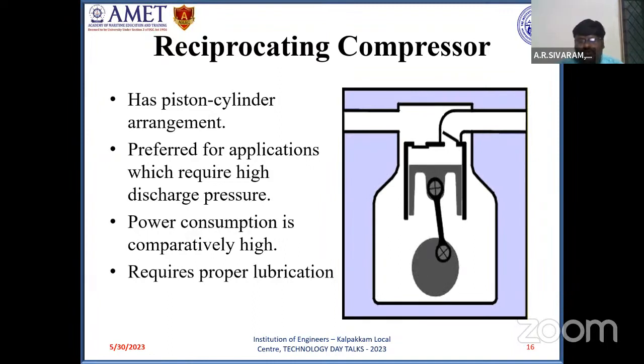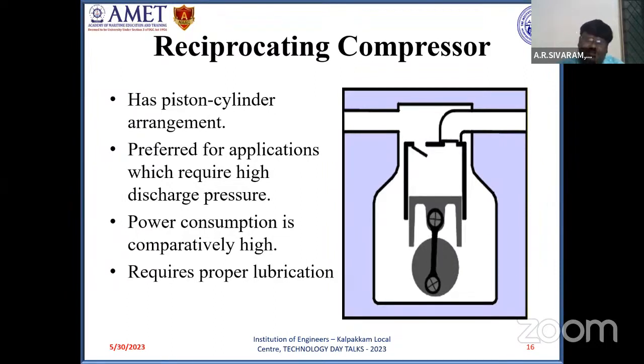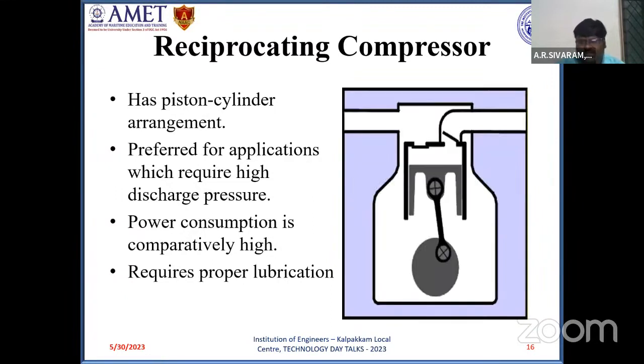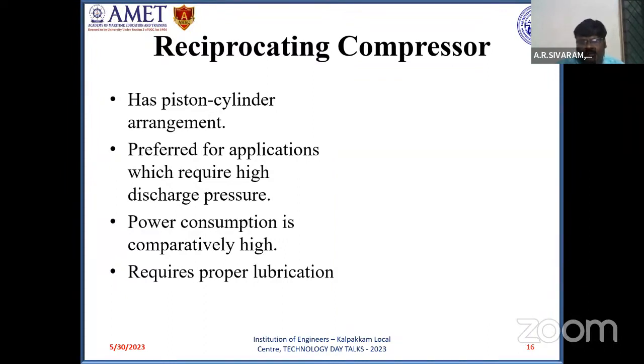During suction, when the piston moves from top dead center to bottom dead center, refrigerant enters, gets compressed in the compressor, and leaves during the discharge stroke at high pressure and high temperature. This is usually preferred where there is a high requirement of discharge pressure, and it requires proper lubrication, because otherwise due to friction the compressor may get damaged. Since it delivers refrigerant at high discharge pressure, the power consumption is comparatively high. Reciprocating compressors are not used for domestic systems; rather, they are preferred for commercial and industrial refrigeration systems, as well as for marine refrigeration systems.